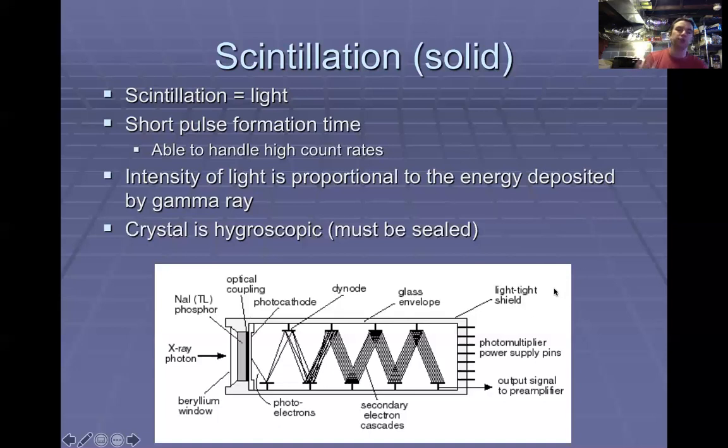Again, you have a dense crystal, much more likely to interact with a photon than a gas fill detector. Gas is not a very dense form of matter. So the crystals are going to be much better at seeing things like low energy photon radiation. And that's actually the main focus of where we use these instruments, for seeing some of our sources that are very low energy radiation.